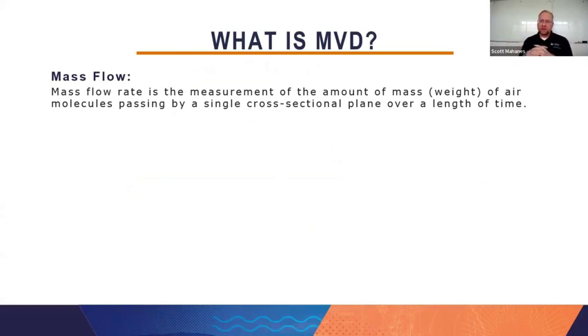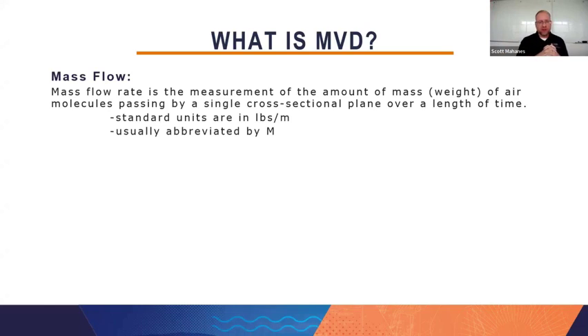Mass airflow is the weight of the amount of molecules passing by a single cross-sectional plane over a length of time. Similar to volume, which is the amount of volume going through that cross-sectional plane over a length of time. But for us, minutes is our time and pounds is our weight. So we're talking about the pounds of air we're moving per minute as our standard unit here. When you see me refer to this in the rest of this presentation, I'll typically call it the capital M value.